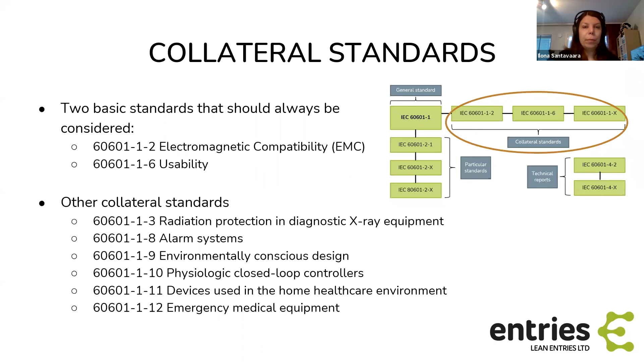Then particular standards. There are both 60601-2-something and 80 standards with the same numbers, and those are both particular standards. The ones beginning with 6 have been made by IEC, and the ones beginning with 8 have been made in collaboration with ISO. So that is the difference here. And multiple particular standards can apply. So if you found one, that doesn't mean that there aren't others. And there are particular standards for things like ECG, EEG, X-ray units, MR equipment, then, for example, dental intraoral X-ray, infusion pumps, medical beds. So a wide selection of devices.